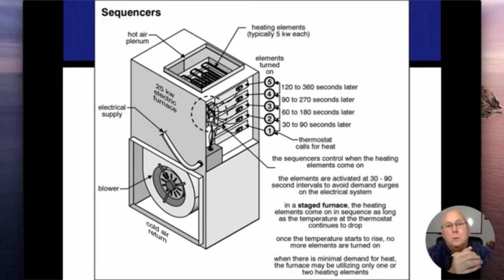All right. So electric furnaces, or electric forced air furnaces, they don't all come on at the same time. There's a sequencer in there. So usually it takes about 4 or 5 minutes or more to go ahead and get all the heat going. But if the thermostat is going up and we're getting heat in there, sometimes they don't all turn on. Plain and simple. They just use whatever burners are needed to produce the amount of heat that's needed. So they recognize the amount of heat that's coming back in the return air, and they're able to see if they need to kick on another one and another one and another one where it comes to it.